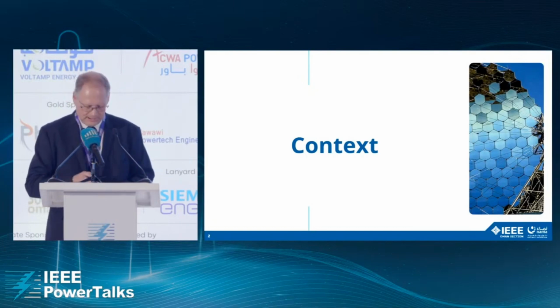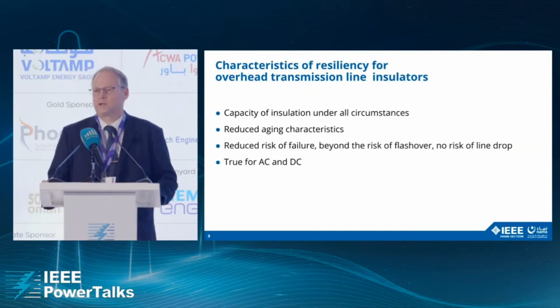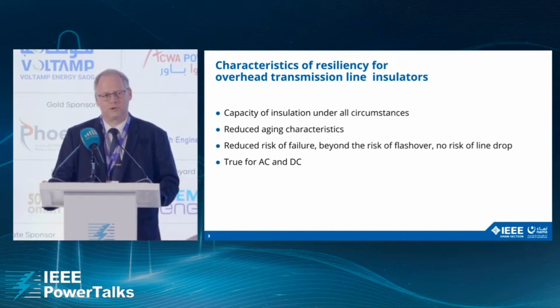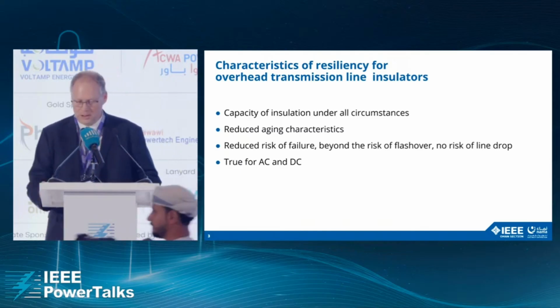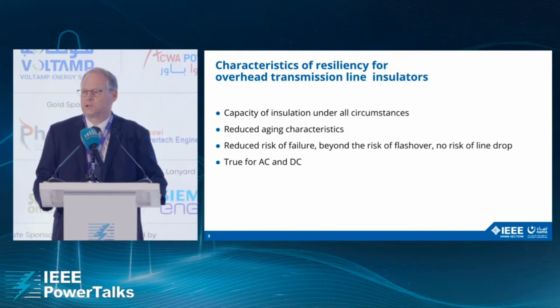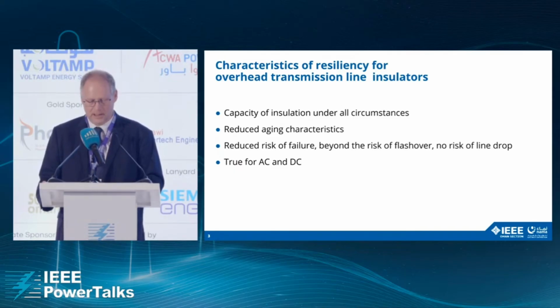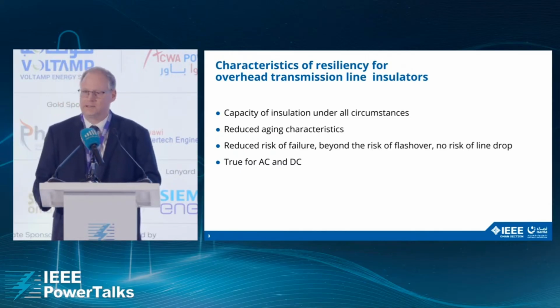So a few words about the context. How do we characterize the resiliency of insulators used on overhead transmission lines? First, it is the capacity to ensure electrical insulation, whatever the circumstances, like meteorological condition and polluted environment. And this presentation will focus on polluted environment. Second, the insulator shall show in service the most reduced or limited aging over time. And third, the insulator shall show the lowest risk of failure. Failure due to electrical flashover, due to pollution, or even complete line drop due to a failure of the insulator. And this shall be true for both AC lines and HVDC lines.